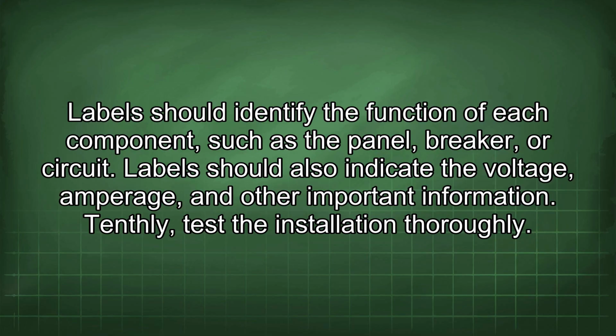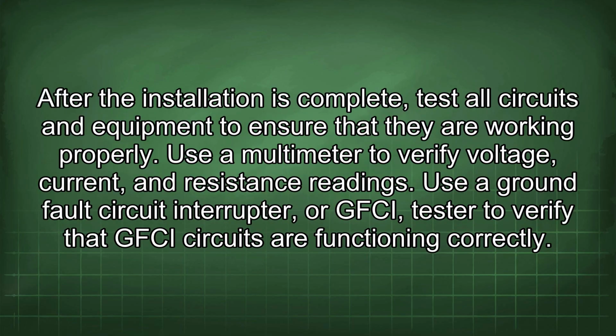Tenthly, test the installation thoroughly. After the installation is complete, test all circuits and equipment to ensure that they are working properly. Use a multimeter to verify voltage, current, and resistance readings. Use a ground fault circuit interrupter, or GFCI, tester to verify that GFCI circuits are functioning correctly.